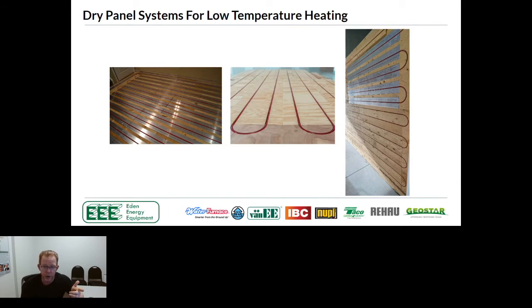So my house where I installed this dry panel, I was heating it with 90 degree water. So if we go back to that COP table and look, okay, what does it look like if we do 90 degree water? Well, that's where you start to see equipment that's performing with a COP of 4 and above. So think about that. If you're getting a hydro bill with this piece of equipment every single month, would you like it to be 200% efficient, 300% efficient, 400% efficient? That's where these discussions happen.